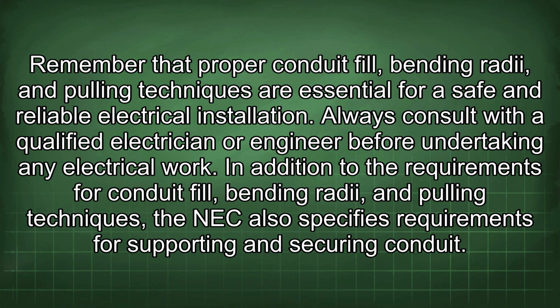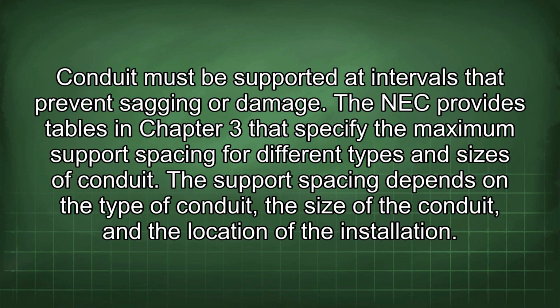In addition to the requirements for conduit fill, bending radii, and pulling techniques, the NEC also specifies requirements for supporting and securing conduit. Conduit must be supported at intervals that prevent sagging or damage. The NEC provides tables in Chapter 3 that specify the maximum support spacing for different types and sizes of conduit. The support spacing depends on the type of conduit, the size of the conduit, and the location of the installation.